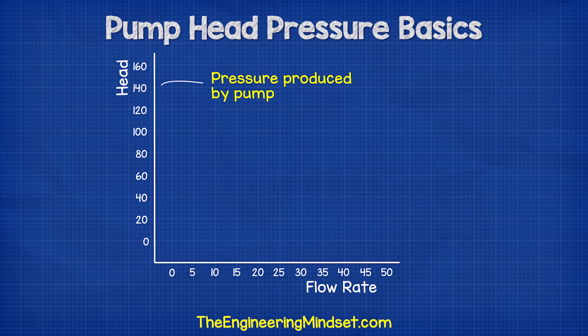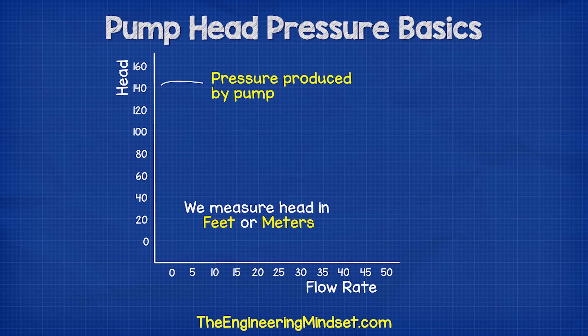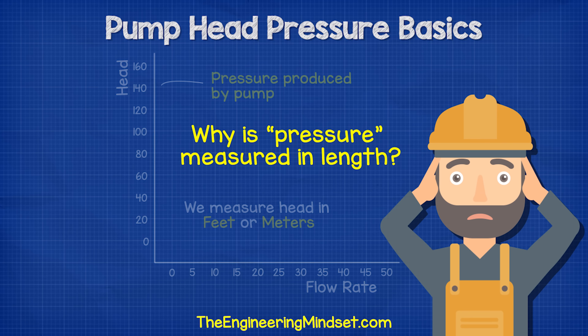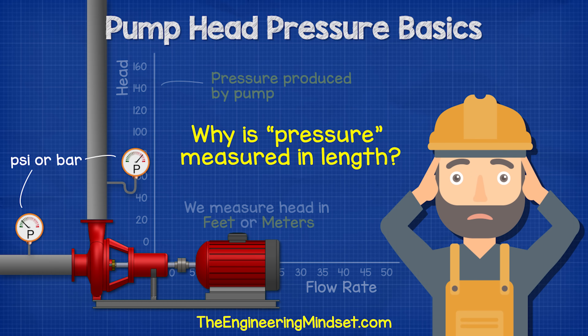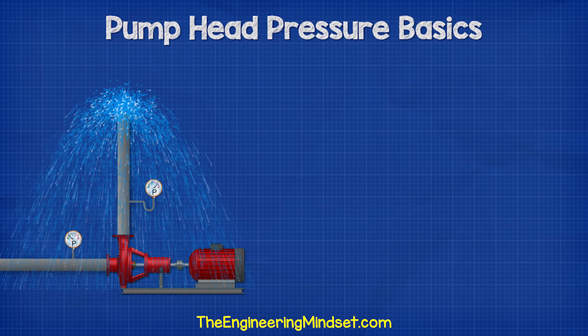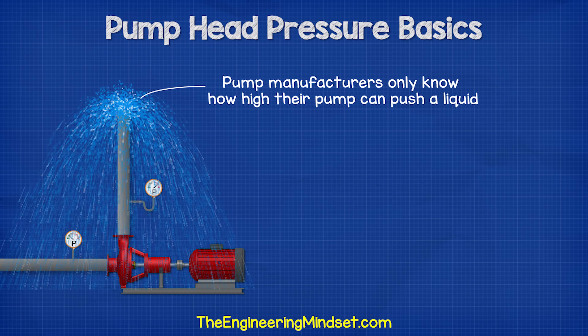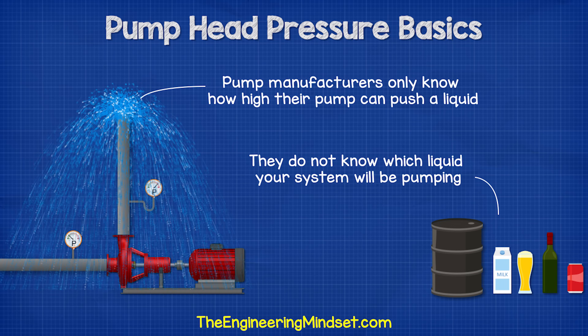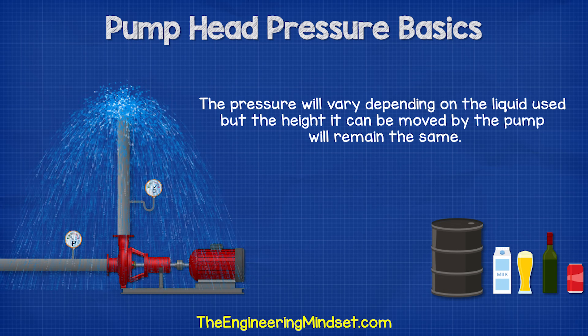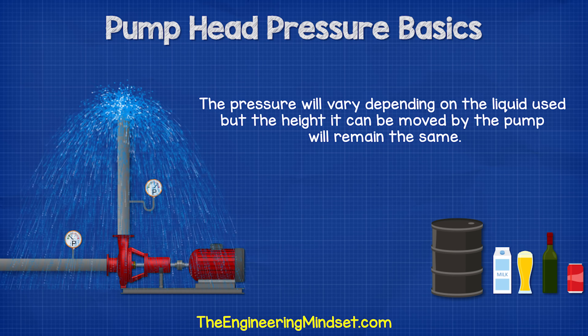Head is shown on the vertical axis and this is referring to pressure, so we often hear the term head pressure. We measure head in feet or meters, which doesn't seem correct considering we're talking about pressure, especially as you see the pressure gauges on the pump typically reading psi or bar. The reason for feet or meters is that pump manufacturers only know how high their pump can push a liquid — they do not know which liquid your system will be pumping, and as each liquid has different properties, the pressure will vary depending on the liquid used.